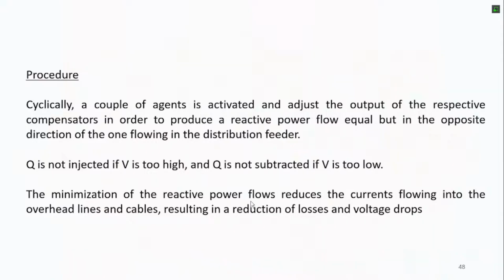The minimization of the reactive power flows is expected to reduce the currents flowing into the overhead lines and cables, resulting in a reduction of losses. And we associate the reduction of the losses with also a reduction of the voltage drops, of the voltage deviation. Indeed, a reduction of the voltage drop means that the energy per charge is decreased. So we can associate the fact that there are less losses into the network with also that the voltage will be more uniform. This is the assumption behind this idea.